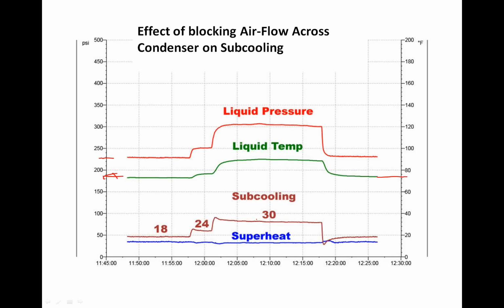You're going, oh, wait a minute now. How's that possible? You told me earlier that if the subcooling changed, the superheat would change because we're changing the amount of refrigerant in the coil. Well, I also told you that the coldest the liquid line could get was down to the outdoor ambient temperature. And what's happening here is every single time we're increasing the pressure, by blocking the condenser, we're changing the design characteristics of the system. In other words, the pressure is rising faster than the liquid temperature.